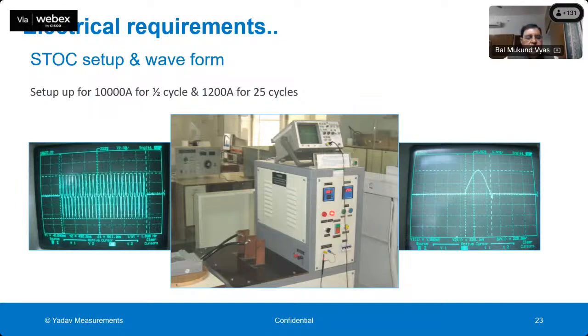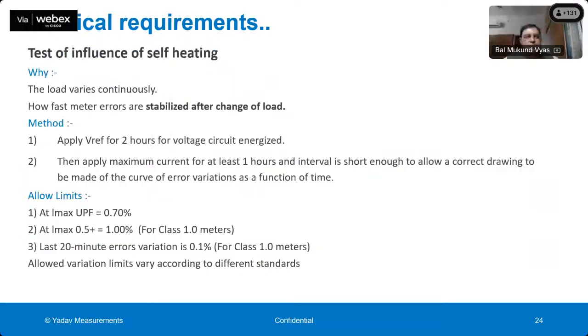You can see here the various types of short circuit current waveforms. On the left side, you can see this 25 cycle short circuit current, which is used for short circuit testing of CTPT operated meters. On the right hand side, you can see the half cycle short circuit current. And these are the various test equipments which are used for testing the short circuit on the meters. There are different tests to be done for a smart meter with a switch. The switch has to be tested with prospective load current and load short circuit current, and you need different types of equipment for testing the smart meter switch.